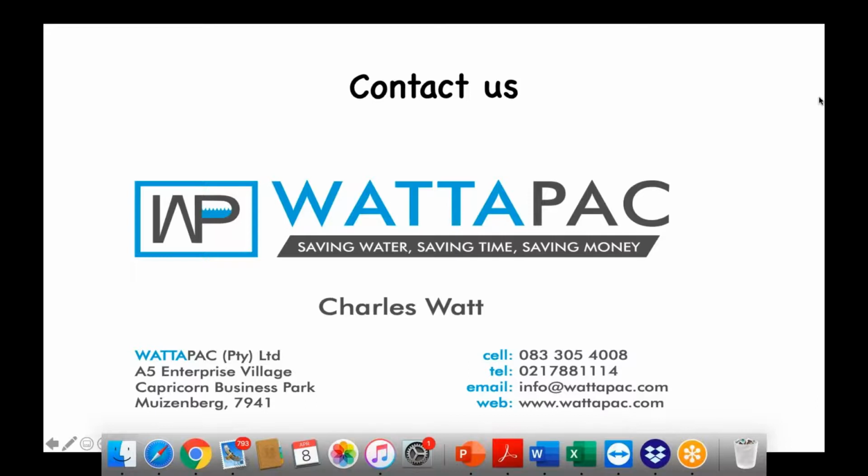We've got plumbers up the West Coast that have very hard water, so they've got a lot of sediment in their water. One plumber just incorporated a filter, which is basically connected onto the bladder itself, which works very well. It takes all the white, calc-type looking sediment out of the water. So there is a solution for dirty water. Obviously, you're going to use your discretion. If you get to a geyser where the anode hasn't been changed for 10 years and the water is completely rusty and red, you're not going to save that water. So you're going to use your discretion as to which water you want to save or not. But most of the water is savable.